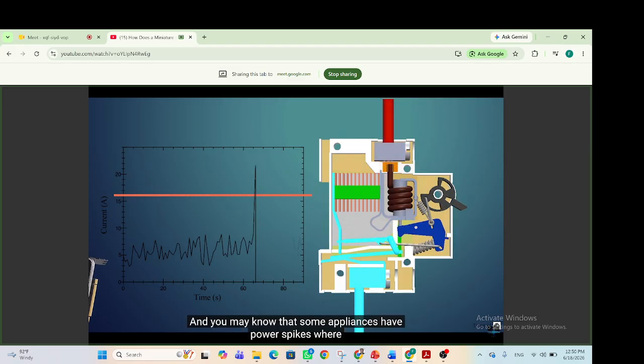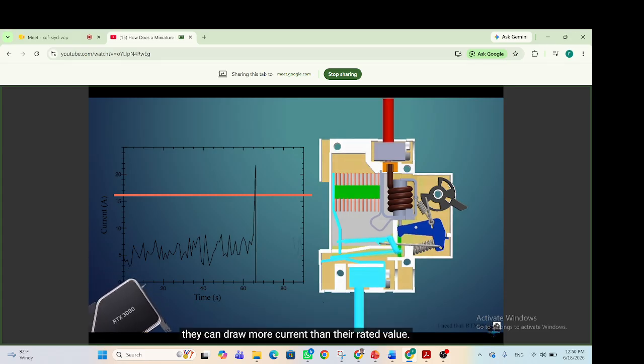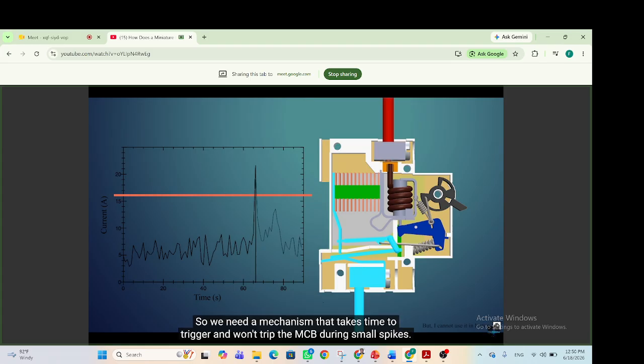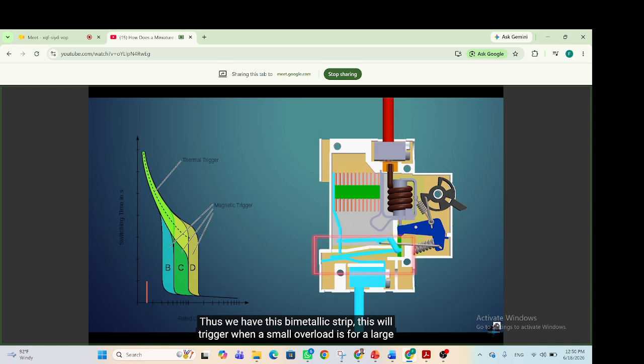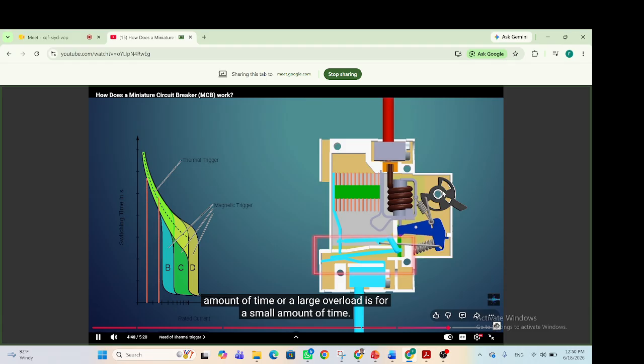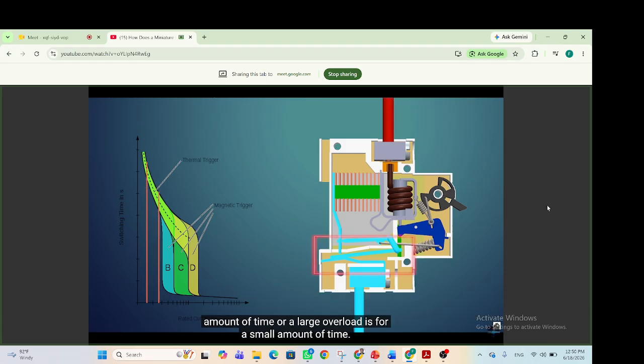Some appliances have power spikes where they can draw more current than their rated value. So we need a mechanism that takes time to trigger and won't trip the MCB during small spikes. Thus we have this bimetallic strip. This will trigger when a small overload lasts for a large amount of time, or a large overload lasts for a small amount of time.